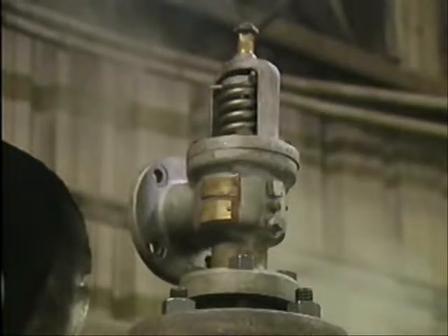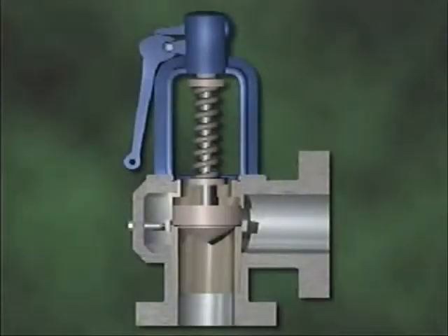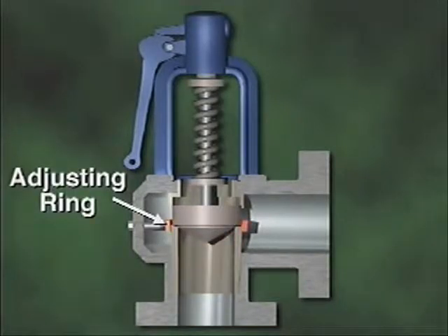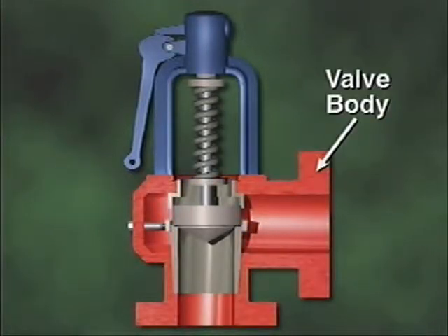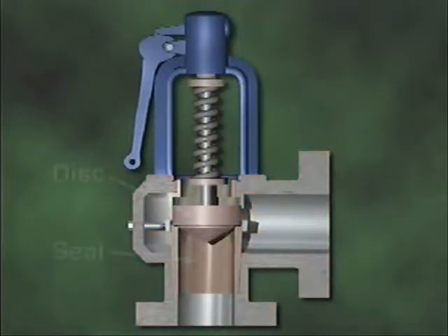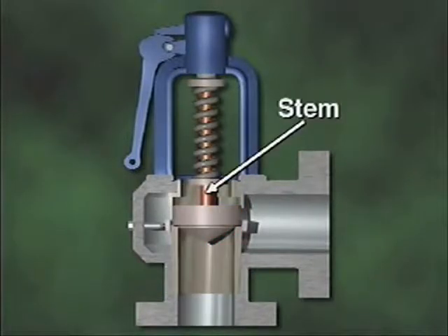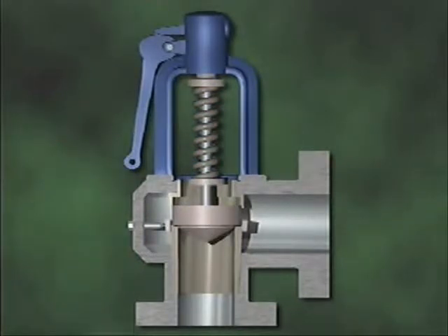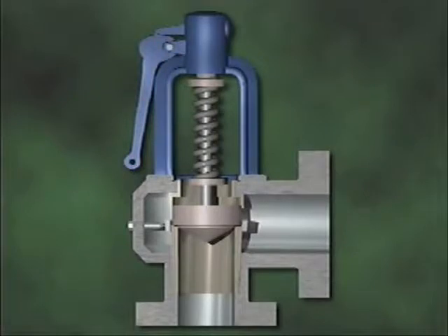In this part, we'll look at a huddling chamber safety valve. This type of safety valve is named for a small space called a huddling chamber located just below the valve's disc. The valve has an adjusting ring used to direct escaping steam toward or away from the disc. The valve body directs the flow of pressurized fluid. The disc and seat seal the system closed under normal pressure. The disc is mounted on a stem, and a spring holds the disc in place while the valve stem transfers tension from the spring to the disc.